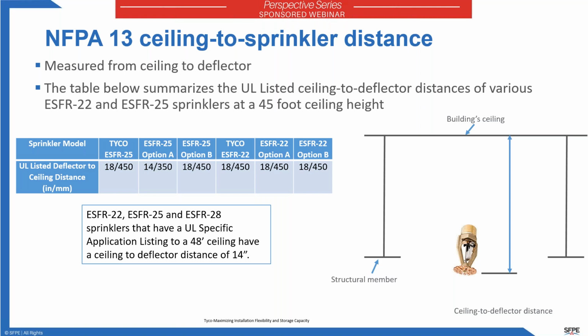So as I mentioned, NFPA 13 measures the sprinkler from the ceiling to the deflector. And if you look, just about all the ESFR 22s that are UL listed for NFPA 13 applications have a ceiling to deflector distance of 18 inches. There are some sprinklers, ESFR 25s, that are approved only with the 14-inch ceiling to deflector distance. Others have the 18.